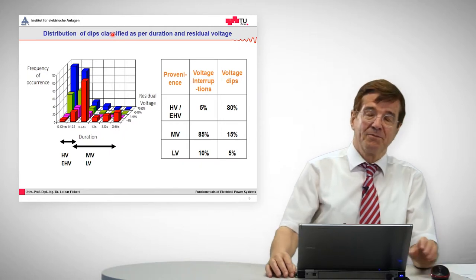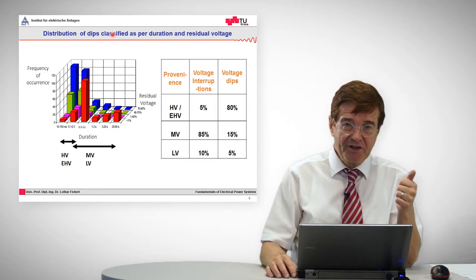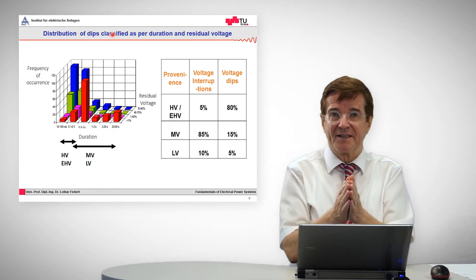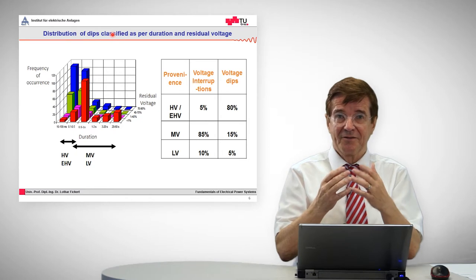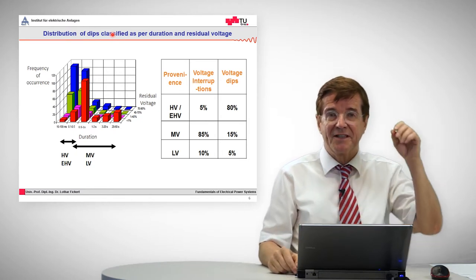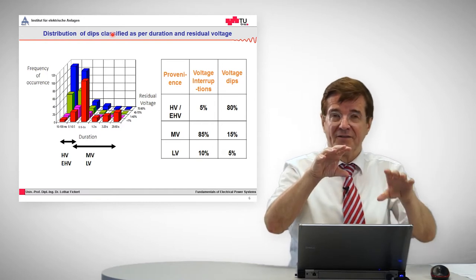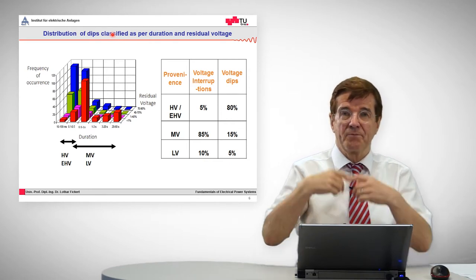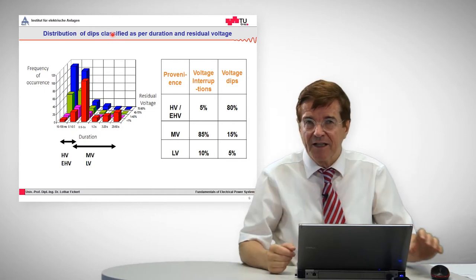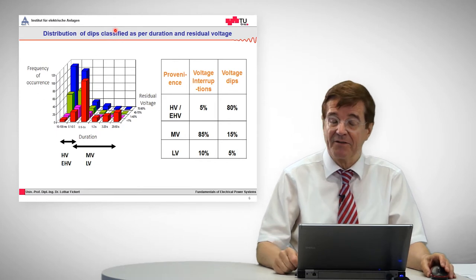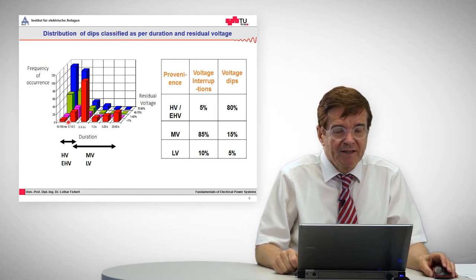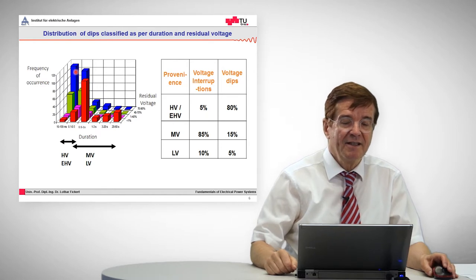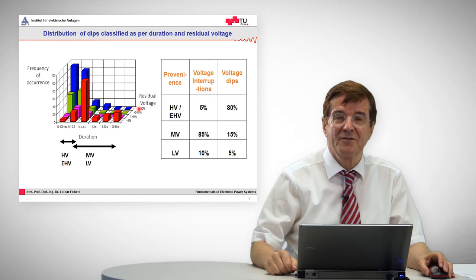One approach is to classify the most important of these events, which are either outages or short interruptions. When you have an interruption in the voltage, electrical processes can no longer take power from the electrical grid. Remember, power in electrical terms is given as the product of voltage and current. So if one of these factors goes to zero — like in an interruption where we have no voltage — then the power delivered is zero and a process will in many cases stop. Therefore, these dips have been investigated, and there is a plot showing the time span of these dips versus the frequency of occurrence and versus the residual voltage.